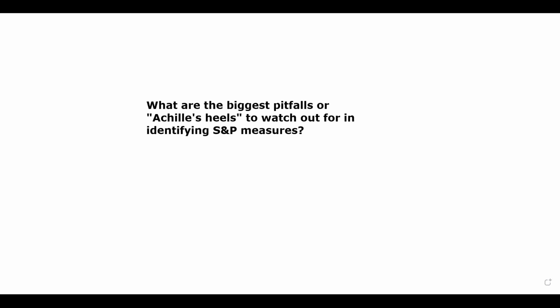And I would add the caveat that more is not necessarily better. Some of our clients want to make several safety and several performance objectives, as in 3, 4, 5 each. And the notified bodies in the MDR world are not looking for that. More is not better. Relevant is better. Now, you don't want to choose one safety and one performance only, but sometimes safety is really the rates of all AEs. That's not very common, but sometimes we do have to revert to that. But I would say typically there's 2 or 3 at the most of each acceptance criteria.